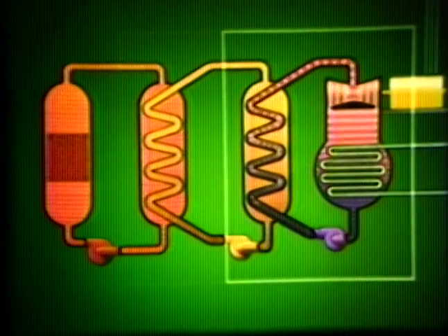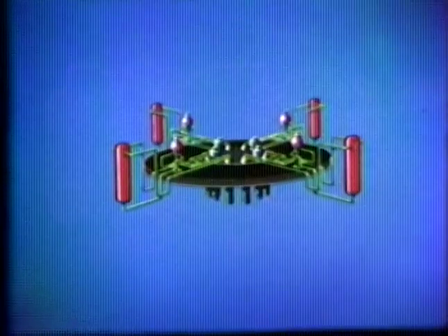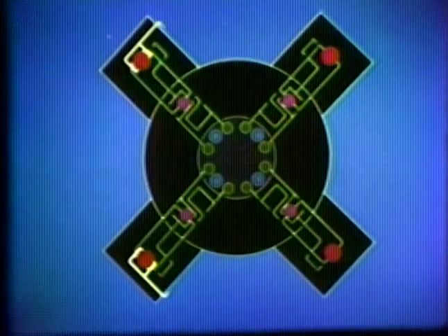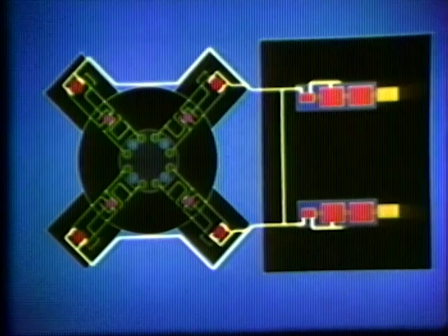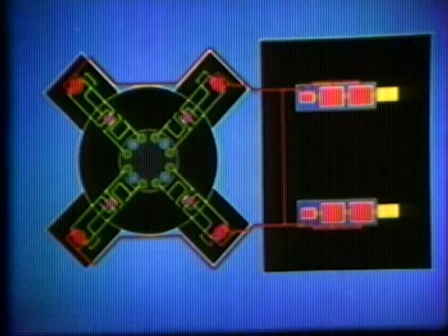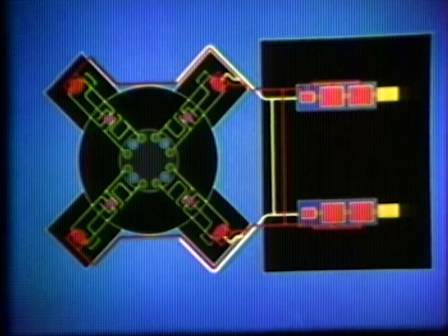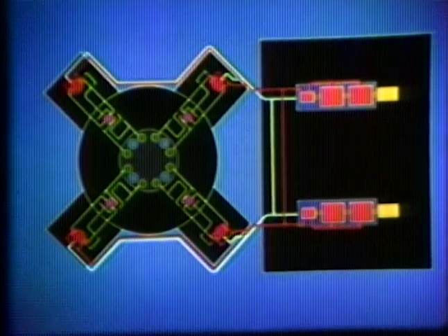The third system is the steam-water system. Steam from the steam generators drives the turbine generators. 2 pipes take the steam from the 4 steam generators to the turbine hall to drive 2 identical turbine generators. It is then condensed, and the water recovered is returned to the steam generators via 2 other pipes. The steam-water system is thus located outside the reactor building.